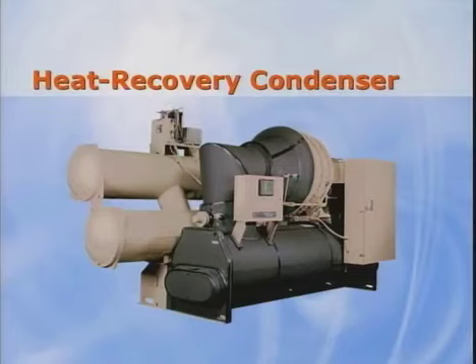Now this is where it gets a little confusing to some people. Any type of condenser that is used to reclaim heat is generally referred to as a heat recovery condenser. But to most chiller manufacturers, such as Trane, the term heat recovery condenser only applies to a secondary condenser of equal size. The amount of heat rejected through a heat recovery condenser is controlled by the temperature leaving the standard condenser. As the water temperature leaving the standard condenser is reduced, the condensing pressure drops and the heat recovery leaving water temperature decreases as well.